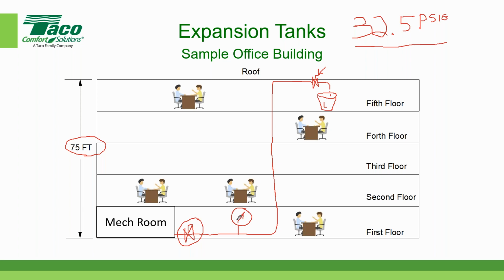And the way I figured that out was I simply took the height of the building, 75 feet, which is the height of my piping system, and divided that by 2.31. The reason I did that is because if I have a column of water, and let's assume this is not to scale relative to the building, this is just a column of water, filled up in this tube. And the height of that column of water is 2.31 feet.